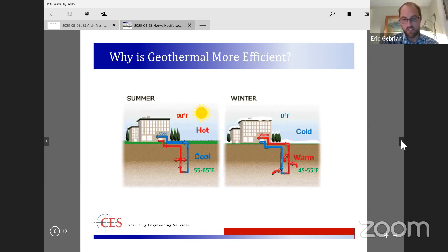Look at the two buildings in the summertime on the left. Let's say you're 90 degrees out and the ground is about 55 to 65 degrees. So we're trying, either with air source, which is the base system, versus geothermal source, to cool the building interfacing with outdoor air that's 90 degrees, or cool groundwater that's 55 to 65 degrees. So you might understand right off the bat why it would be more efficient to cool with groundwater.